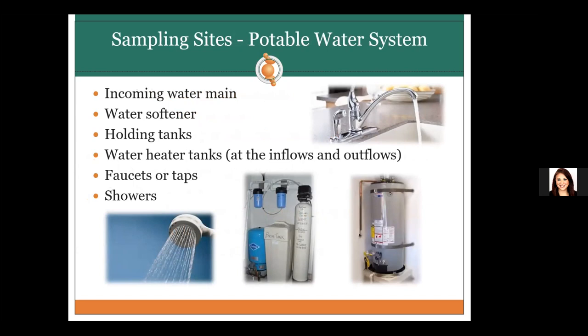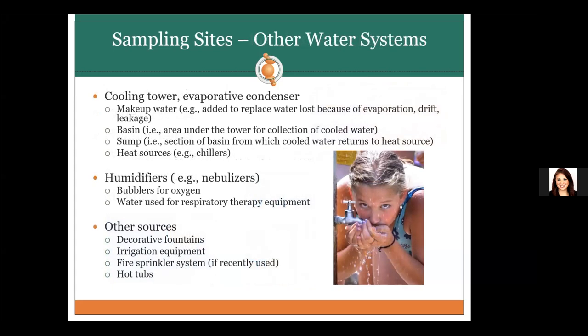For sampling potable water systems, focus on the incoming water mains, water softeners or holding tanks, water heating tanks, faucets and taps, and showers. For other systems such as cooling towers, check for recently added makeup water, water basins, water sumps, and other heat sources. You can also check humidifiers inside rooms, bubblers for oxygen, or water used for respiratory therapy equipment. Other water sources include decorative fountains, water fountains, irrigation, fire sprinklers, hot tubs, and swimming pools.